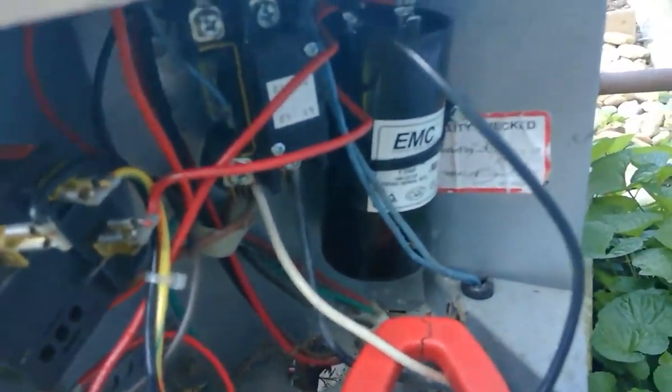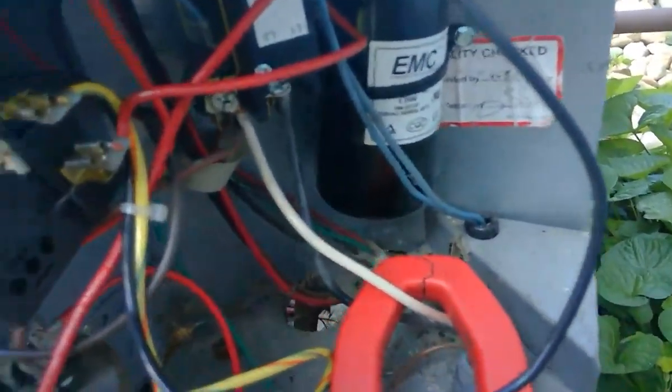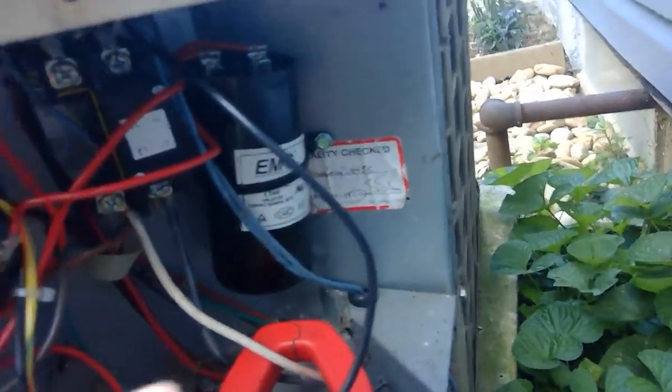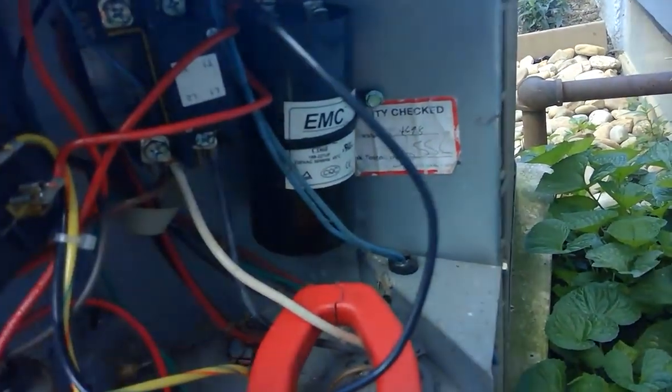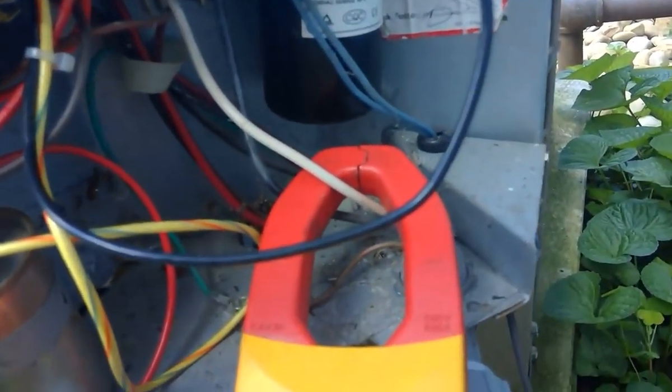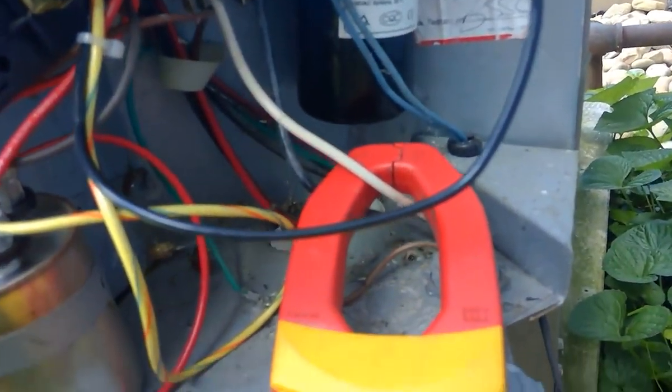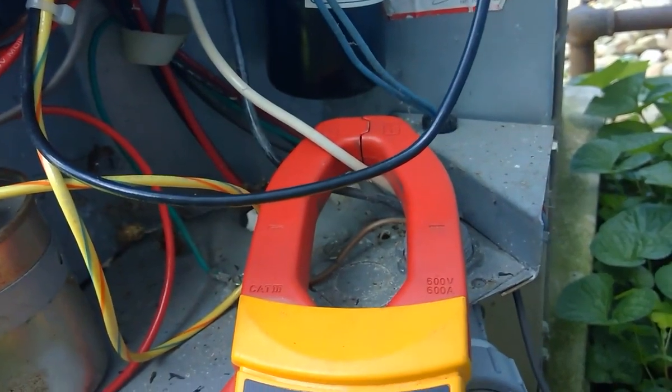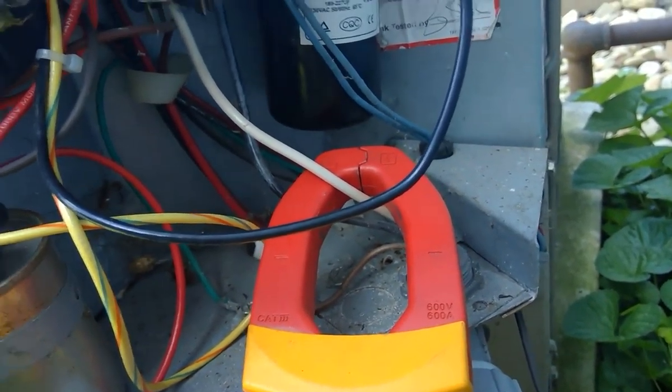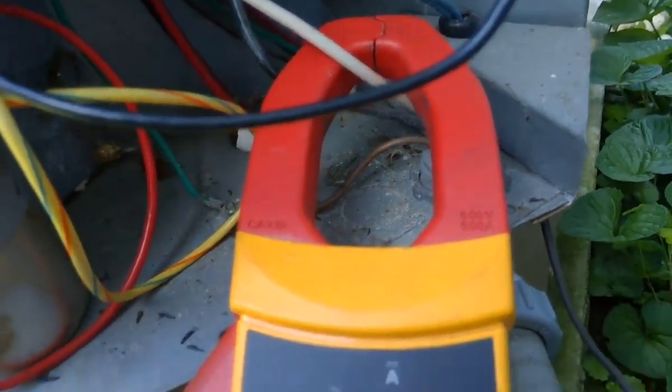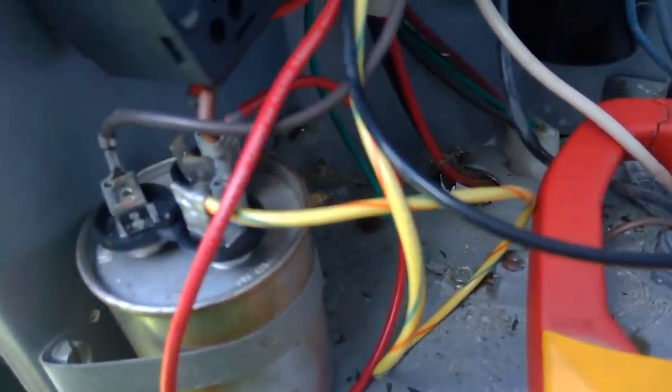So anyway, I did go ahead and get the 521 kit connected up. And if you can see right there, there's the relay. I put the capacitor over here, you can see over there. And basically wired it up according to the instructions. So the black goes to the contactor. The red goes to the common on the existing capacitor. And the yellow goes to the herm on the existing capacitor.